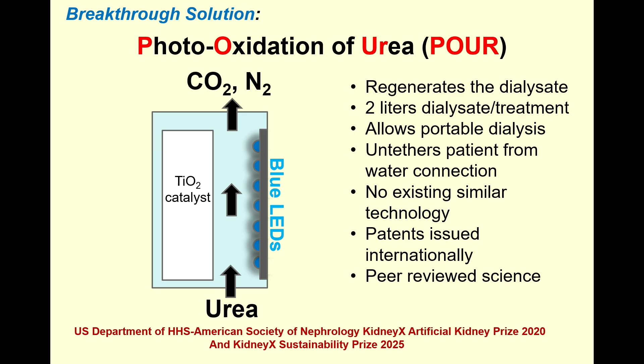It just shows, again, kind of a little animation. So off to the left would be the patient, and there's the dialyzer, the hollow fiber dialyzer. And in the dialysate loop, we would be circulating the urea, which is in the dialysate. The hollow fiber device takes it from the patient, circulates it through the photo-oxidation unit, which is to the right, and then clean dialysate comes back to the patient, and the urea is gone.